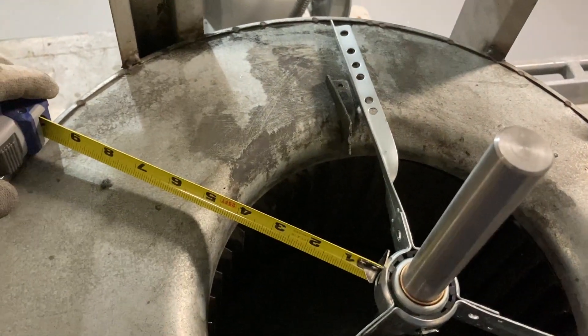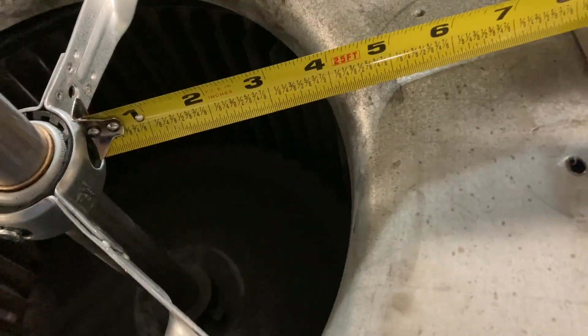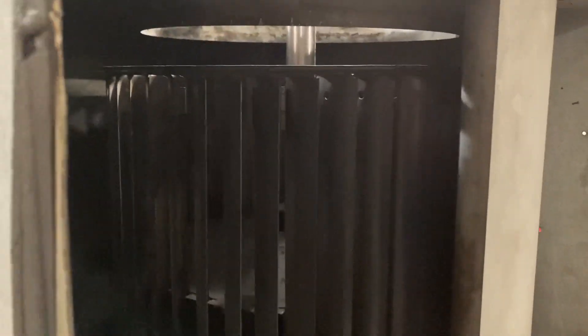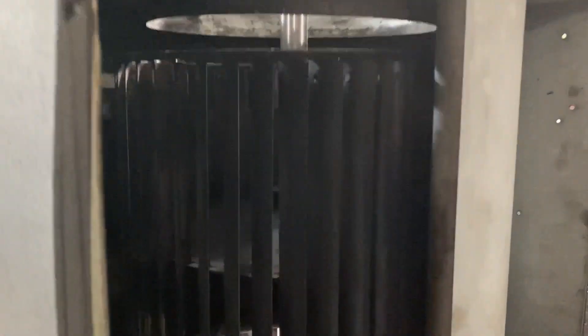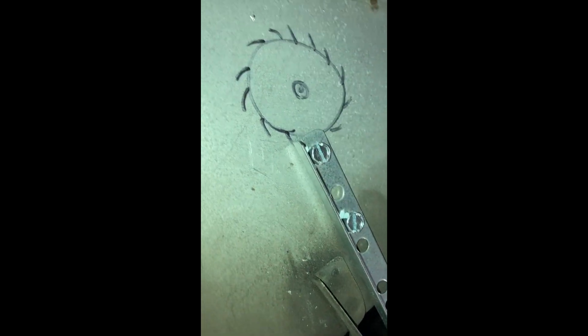I'm just lining everything up, taking measurements all the way around, making sure everything looks even and centered. Once the blower wheel looks centered in there, I'll attach these on one side, then flip the housing over and do the same on the other side. I'm looking at the spacing, the gap. You simply install it with the supplied hardware.